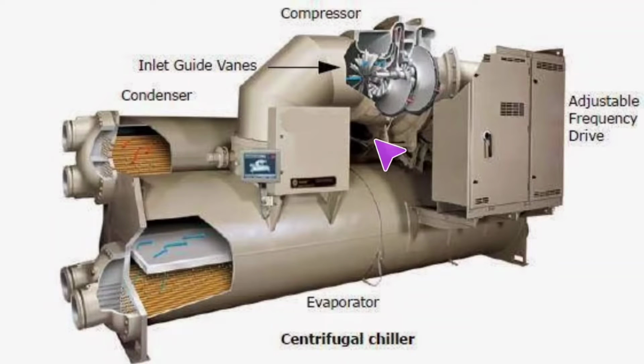Now, these machines that we're specifically discussing are still low pressure machines, which means that they're either running a 123 or an R11 on some of the older ones. A majority of your new ones are going to be 123, and the newest ones that are coming out, they are developing some other refrigerants. I'm not exactly sure which ones they're going to commit to. There's several that have been discussed over time, but none of the manufacturers have outright committed to one specific refrigerant at this time.